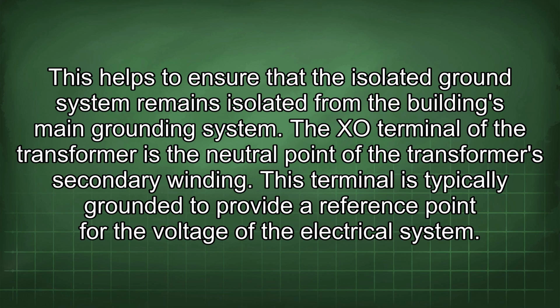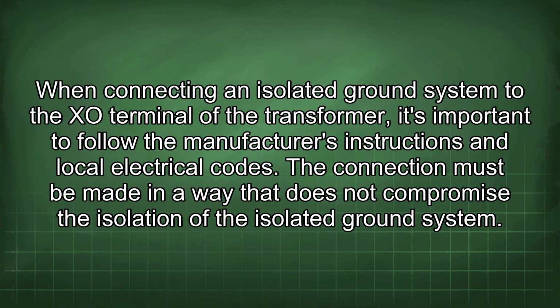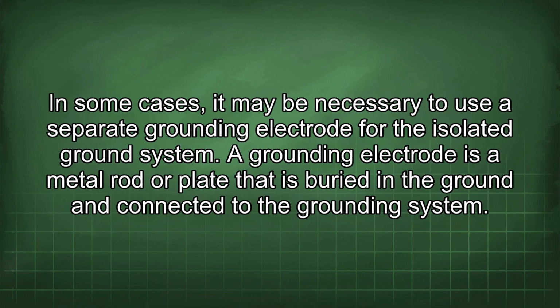The X0 terminal of the transformer is the neutral point of the transformer's secondary winding. This terminal is typically grounded to provide a reference point for the voltage of the electrical system. When connecting an isolated ground system to the X0 terminal of the transformer, it's important to follow the manufacturer's instructions and local electrical codes. The connection must be made in a way that does not compromise the isolation of the isolated ground system. In some cases, it may be necessary to use a separate grounding electrode for the isolated ground system.